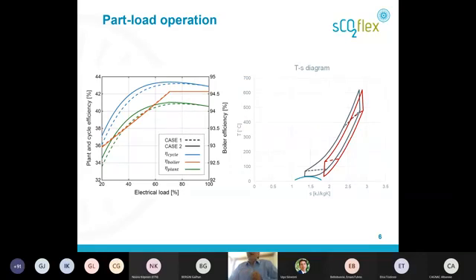We can see the red curve is the efficiency of the boiler that practically remains constant down to 70% of the load, then goes down quite linearly due to the increase in the air to fuel ratio. What about the cycle? The cycle has a slight increase of the efficiency at part load due to the fact that the heat exchangers are somewhat over-designed at part load, and then the efficiency drops due to the efficiency of the turbomachinery, of course. But as an overall effect, we can say that the plant efficiency is quite stable and quite high. The maximum is at 70% of the load, and then goes down slowly until 50%.